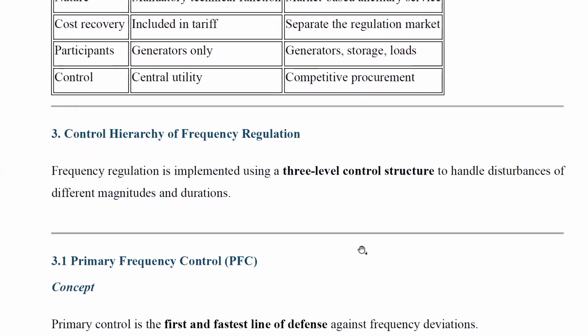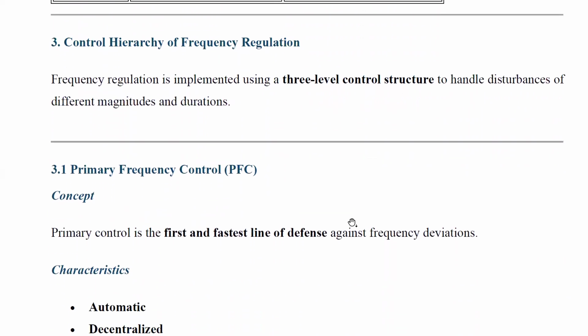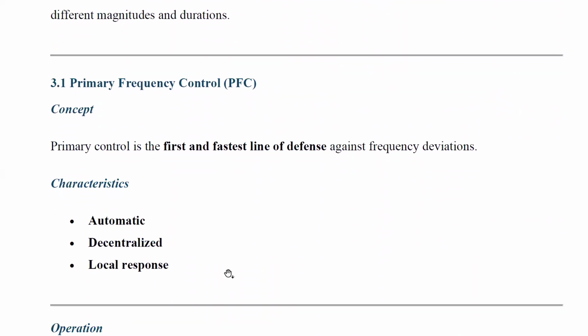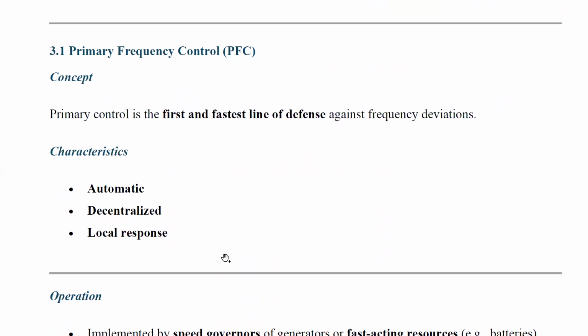Next comes the control hierarchy of frequency regulation. Frequency regulation is implemented through a three-level control structure to handle disturbances of different magnitudes and durations. First comes the primary frequency control. What is primary control? Primary frequency control is the first and fastest line of defense against frequency deviation. Its main characteristics are that it is automatic, decentralized control, and based on local response.